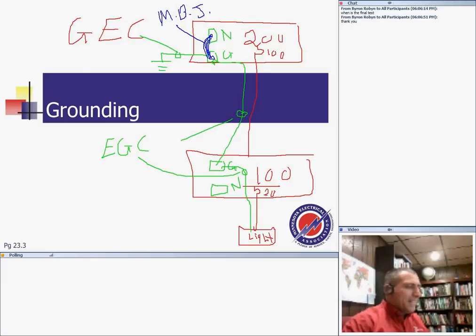Oh, okay. So it doesn't work today because the transformer neutral was not bonded. Oh, you're lucky if the light doesn't work. If you don't bond the neutral, and if the neutral is for whatever reason disconnected, you can literally burn the building, because your neutral and everything is shared between the 240 or the 480 or the 208 system. So a neutral that's not bonded is a big deal.